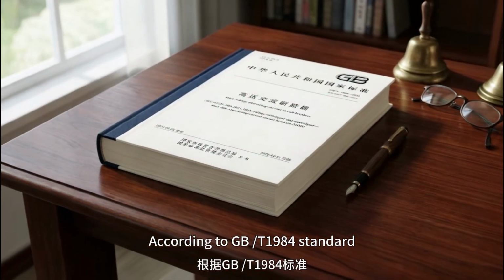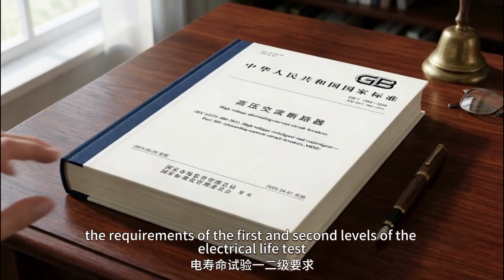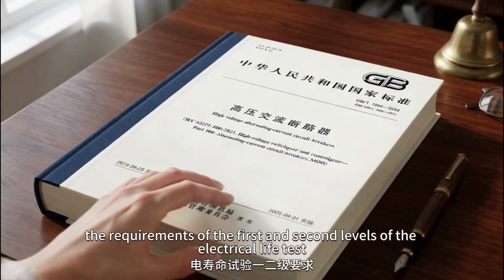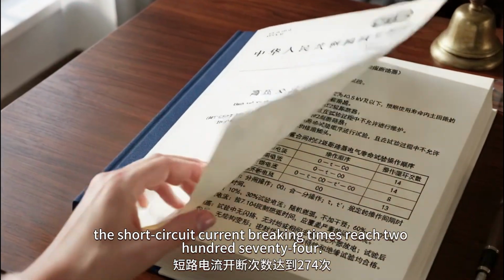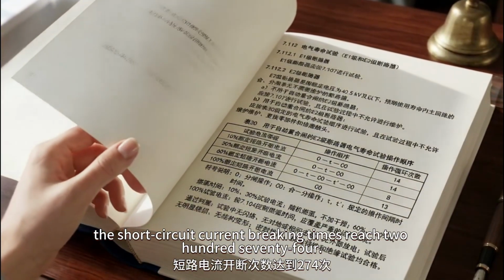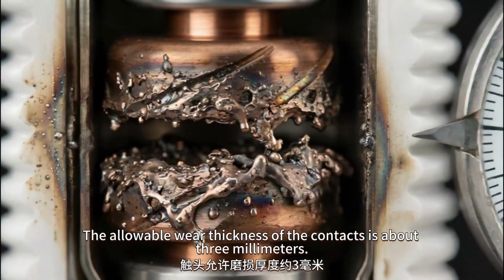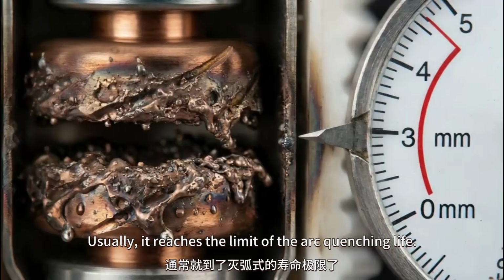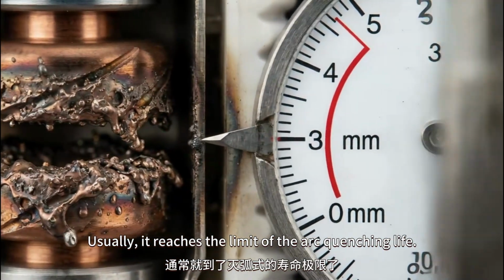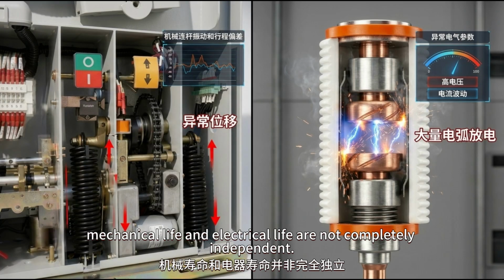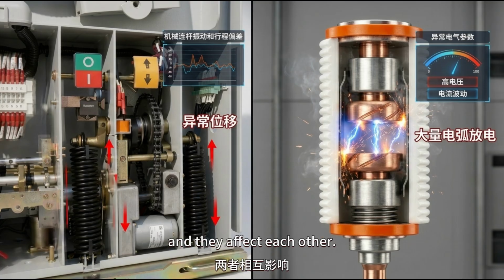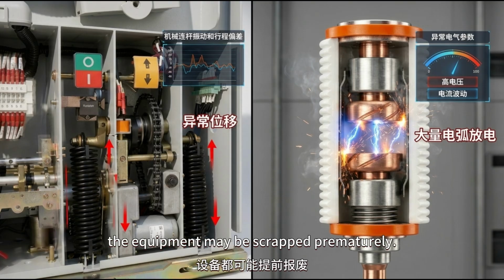According to the GB/T 1984 standard, the requirements of the first and second levels of the electrical life test, the short circuit current breaking times reach 274. The allowable wear thickness of the contacts is about 3 millimeters. Usually, it reaches the limit of the arc quenching life. More importantly, mechanical life and electrical life are not completely independent, and they affect each other. If either one reaches the limit first, the equipment may be scrapped prematurely.